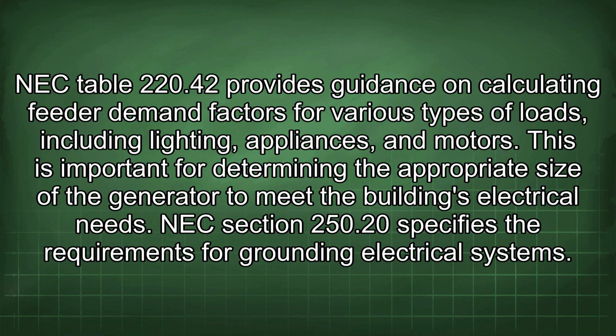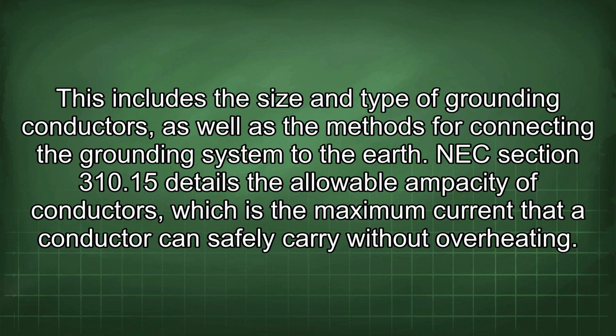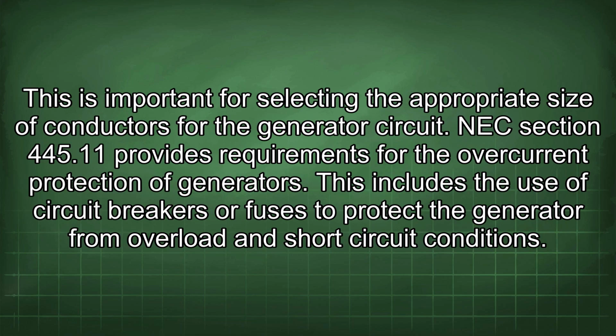NEC Table 220.42 provides guidance on calculating feeder demand factors for various types of loads, including lighting, appliances, and motors. This is important for determining the appropriate size of the generator to meet the building's electrical needs. NEC Section 250.20 specifies the requirements for grounding electrical systems. This includes the size and type of grounding conductors, as well as the methods for connecting the grounding system to the earth. NEC Section 310.15 details the allowable ampacity of conductors, which is the maximum current that a conductor can safely carry without overheating. This is important for selecting the appropriate size of conductors for the generator circuit.